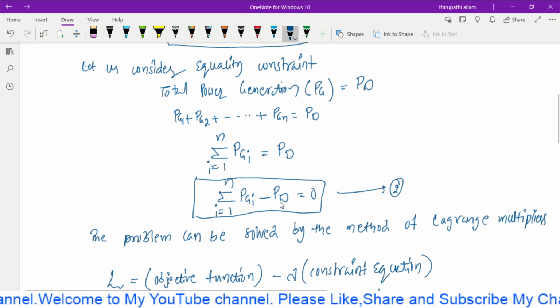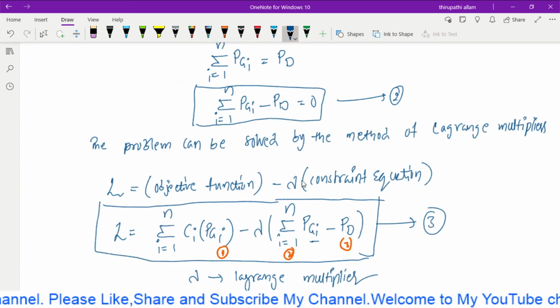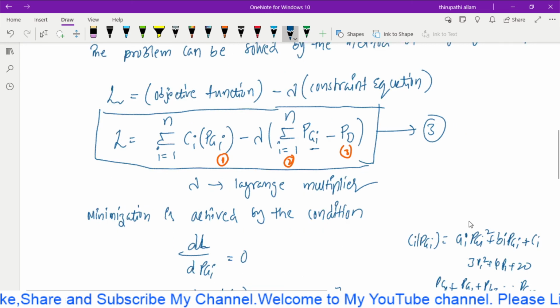In the Lagrange multiplier method, you write the equation L equal to objective function minus lambda into constraint equation. So here the objective function is summation i equal to 1 to n Ci of PGi, minus lambda summation i equal to 1 to n PGi minus PD. Lambda is the Lagrange multiplier. Now minimization is achieved by the condition that the derivative of the Lagrangian with respect to power generation PGi equals 0.